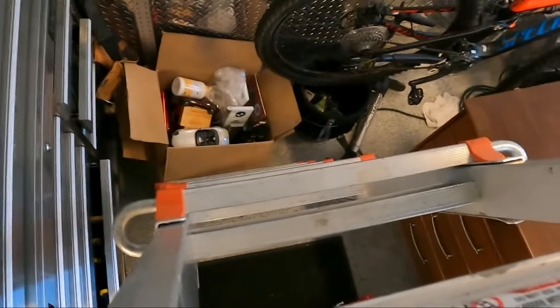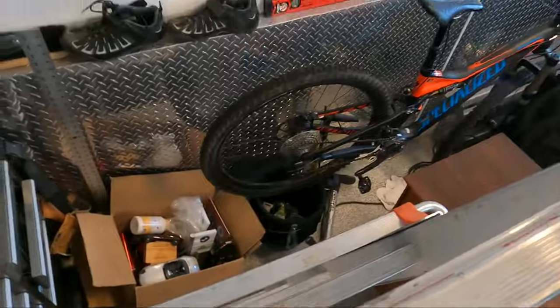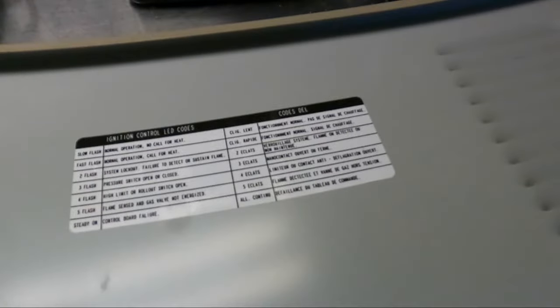So we go down and we look at our outside panel that we pulled off. There's going to be a readout of what those codes represent. As we'll notice here, number four is for limit switch open.